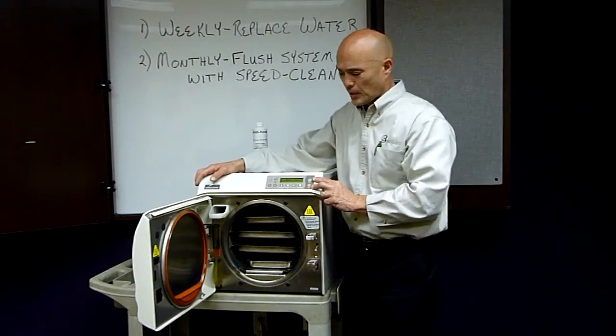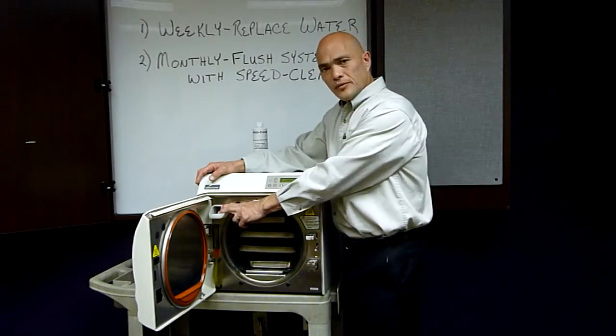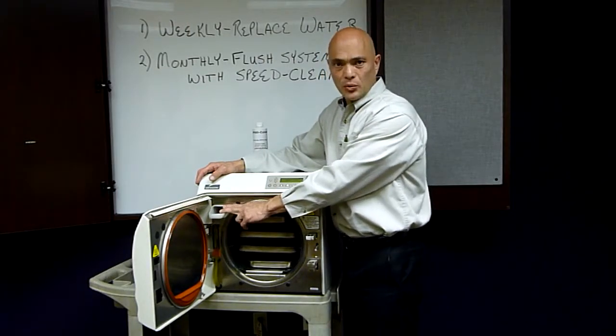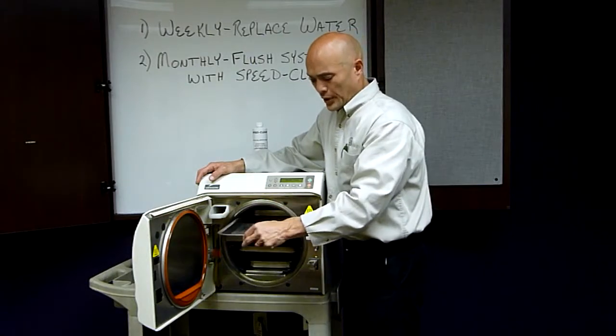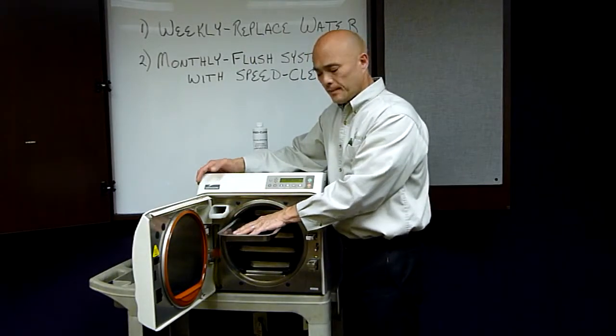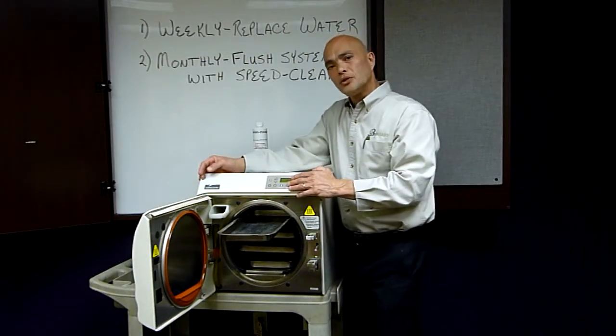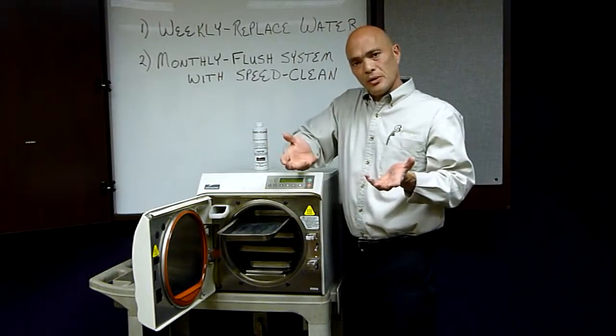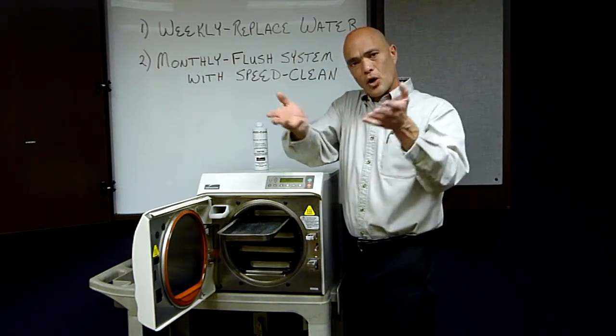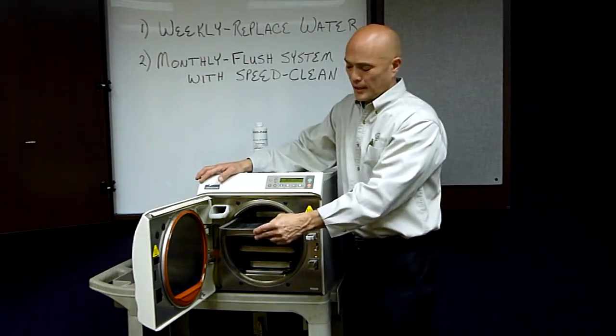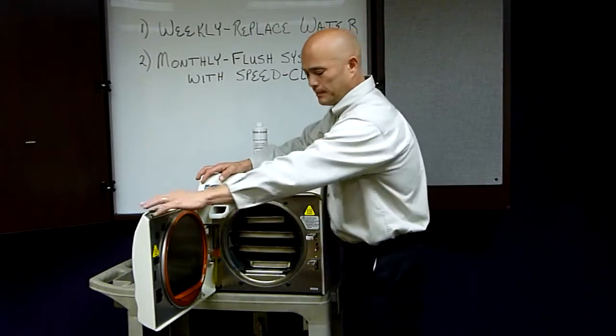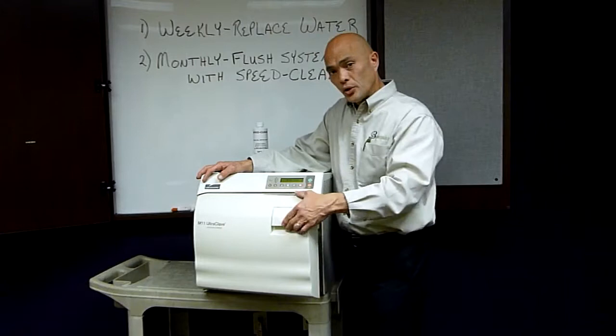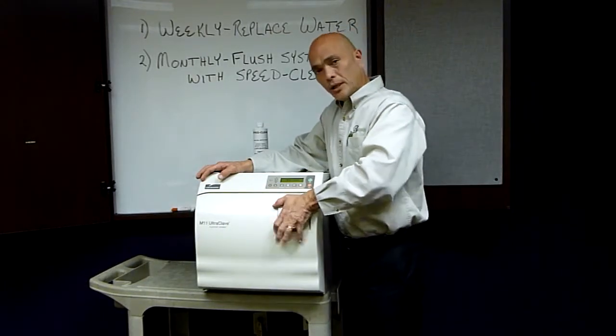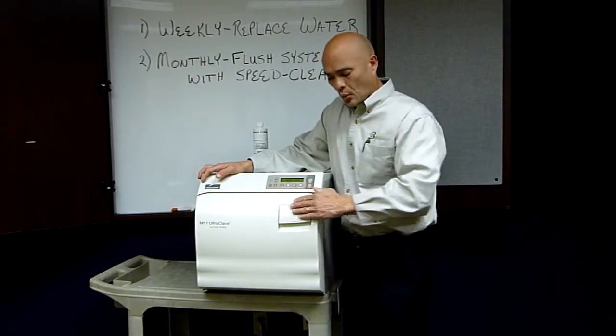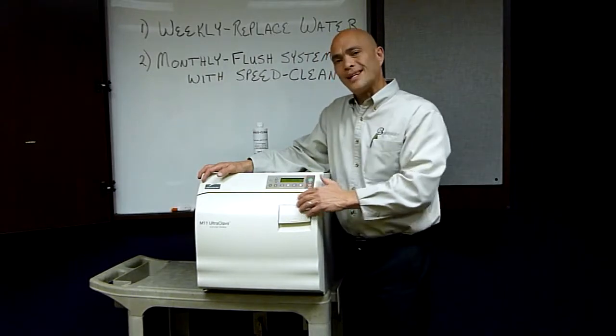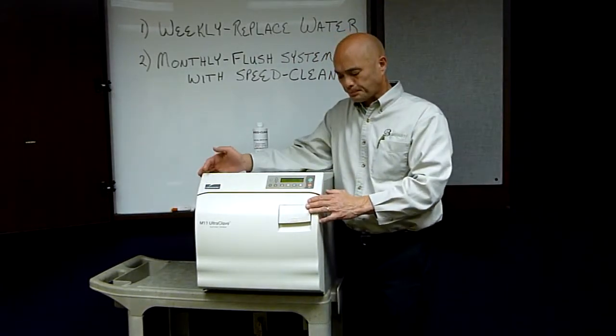Operation of your sterilizer. To start with, you want to make sure your reservoir is filled with 1.4 gallons of distilled water. Put the items you want to sterilize on the trays. Make sure that you don't overfill your chamber. You want the steam of your sterilizer to be able to go around all the packs, and therefore you don't want to overfill it. Push the trays in, close the door. To close the door, you want to slightly lift up on the handle, push in, and then push down on the handle. When it's nice and smooth across here, that indicates the door is closed all the way.